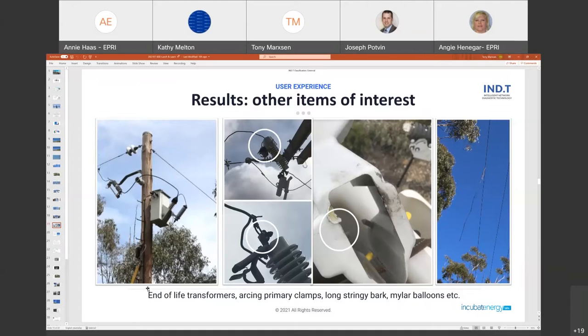Problem found. The middle one is loose clamps, arcing clamps - we've seen a few of those, and they generate quite a lot of radio frequency signal. This one was in the US; we've seen similar here in Victoria. You can see they generate quite a bit of heat and start to melt the plastic guard.